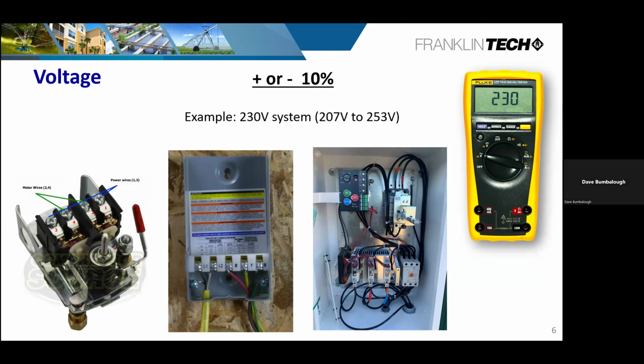So when you're at, say, a pressure switch, a control box, or even a panel, we're measuring that voltage coming in. It should be within that plus or minus 10% of what the equipment is rated for, not the power supply rating. So for example, if you're hooking up a 230 volt system, you want to stay somewhere between 207 and 253. That is the norm. If it ventures outside there, you start having component failure, you start stressing, say, the wires inside, and some of the other protection devices start misbehaving. So you can have all kinds of issues start popping up if that is not in check.